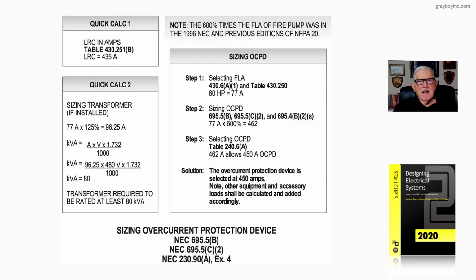Now, sizing a transformer if it's installed, and I'm talking about a separately derived system somewhere, we would take the 77 amps times 125%, which is 96.25. The kVA is amps times voltage times the square root of 3, because it's three-phase, divided by 1,000. Then we would have 96.25 times 480, the voltage, times 1.732 divided by 1,000, and your kVA rated transformer would have to be at least 80 kVA.